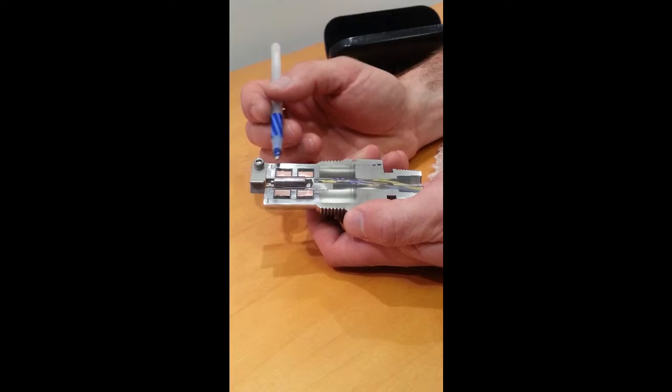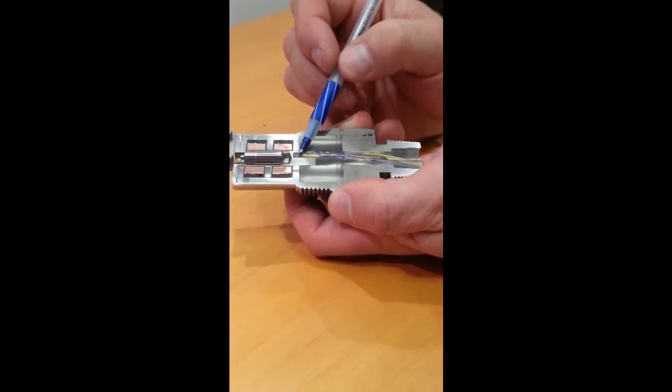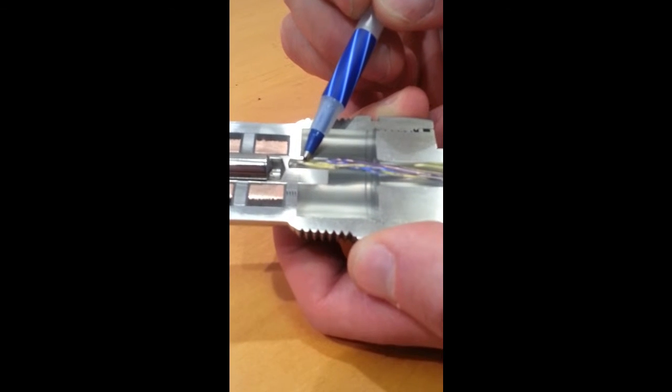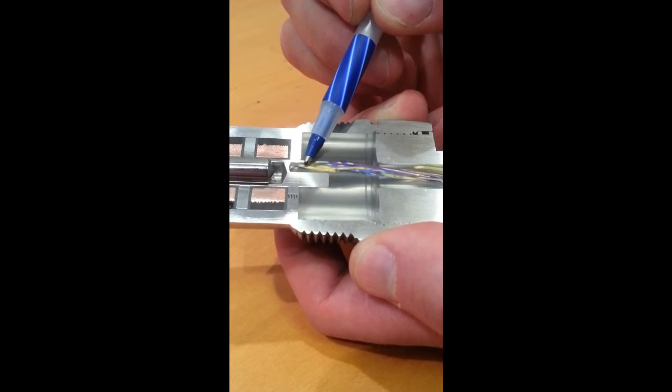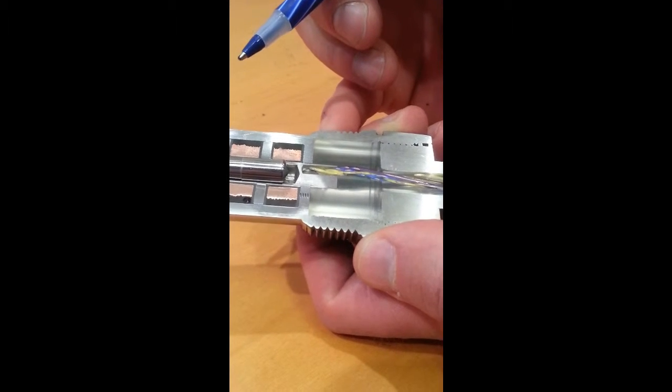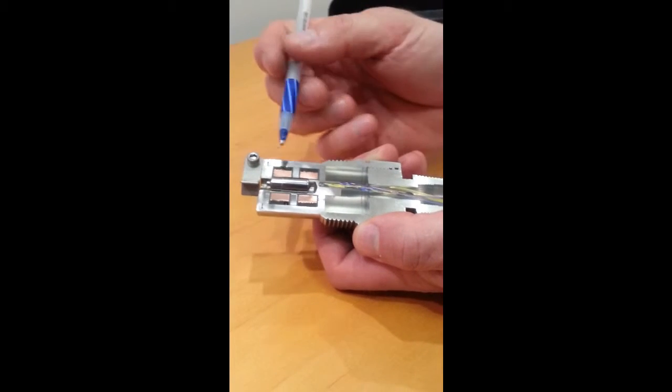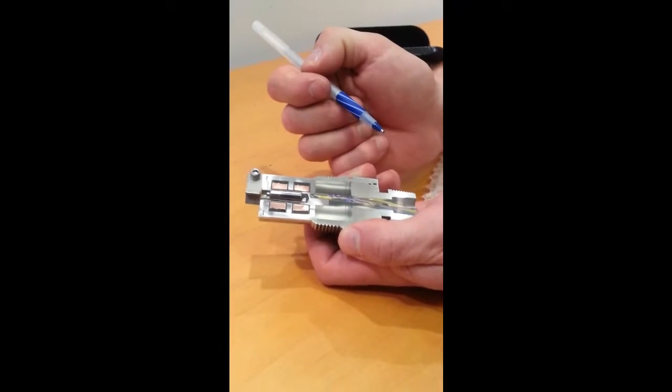We're measuring viscosity here with the coils. Right below the piston sensor chamber here is an embedded platinum RTD. That RTD measures temperature. So when this is inserted into a pipe or into a tank, this sensor will come up to the same temperature as the process. So the coils measure viscosity.